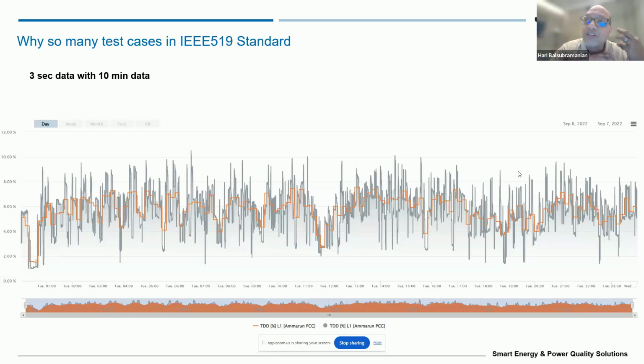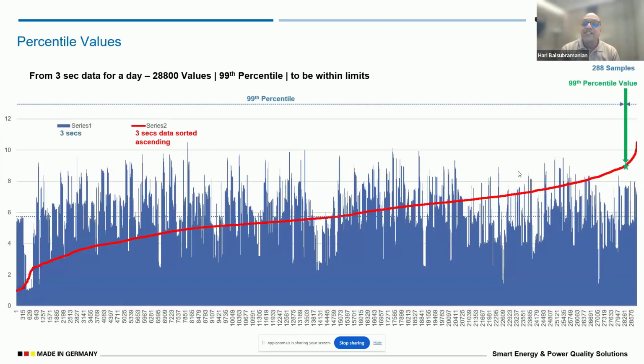So there are three limits which we need to consider when you are monitoring for IEEE 519. In other words, the last one percentile value can be beyond a certain value. For 3-second values, 99 percent of the time you should be within the limit, and one percent of the time you can be above the limit and still pass the IEEE 519 standard. So this graph explains very clearly how the percentile calculation is done as well.